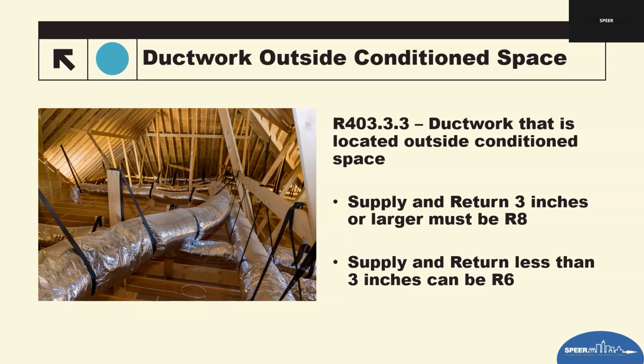Contractors should avoid, and we'll talk about these later on in the presentation, compression of duct insulation, especially when strapping ducts across framing members, which they should not be in contact with. Compressing the insulation does not maintain its rated R value and could render it non-compliant. Any duct outside conditioned space will lose heat energy unless it is properly insulated. So the R8, R6 requirements are straightforward, powerful in reducing HVAC run time, improving comfort, and lowering utility bills.